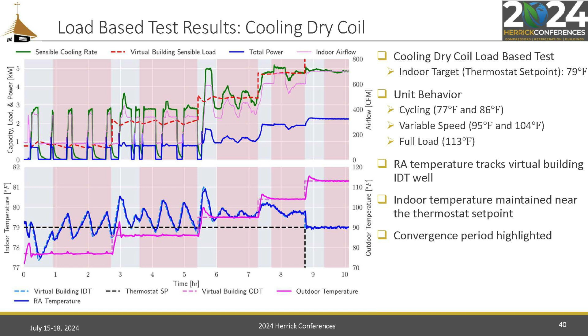So in the first couple of test conditions, if you look at the upper graph, you can see the compressor is turning on and off. The blue line is the total power, and the green is the cooling rate, and you can see them both going on and off together because the load is so small that it's cycling. That unit, variable speed systems don't vary down to almost zero.